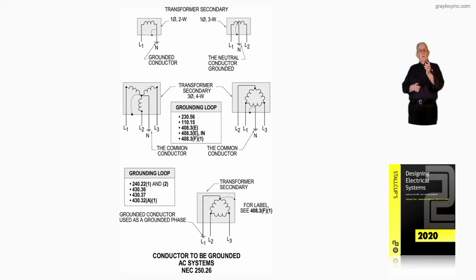But now notice that Y system you see right in the center there, of the grounding loop and the transformer above it, three phase. It's a Y, and you have to worry about harmonics. So if you have harmonics, nonlinear loads, double it in size. Or you have to have a K-rated transformer to allow for that. Now, you can pull three hots with one neutral.